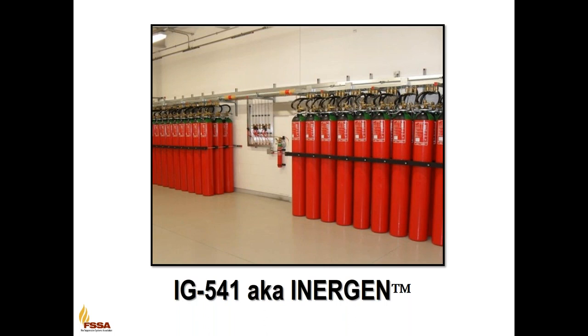Inergen suppression systems are based on the principle of reducing the oxygen concentration inside the protected hazard. Each system is designed to decrease oxygen to a specific level. When discharged, Inergen is quickly and uniformly distributed within the enclosure, achieving design concentrations in 60 seconds for fast growth fire hazards and 120 seconds for slower growing fire hazards.